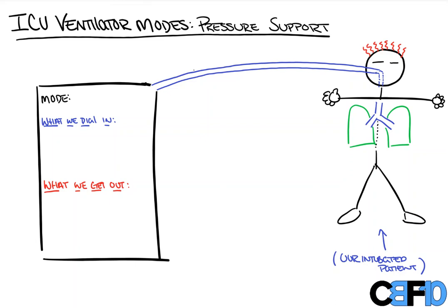We have our ventilator over here on the left side, and we're going to say that our mode is PS for pressure support. We're going to talk about what we dial in, then we're going to discuss what the machine actually does, and then what we get out as a result. The only thing we're going to dial into this is a pressure, and this is going to serve as our support.